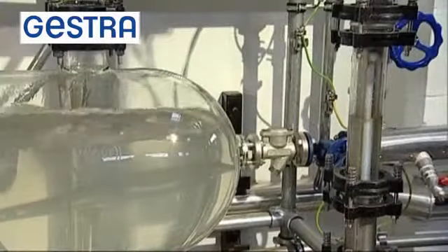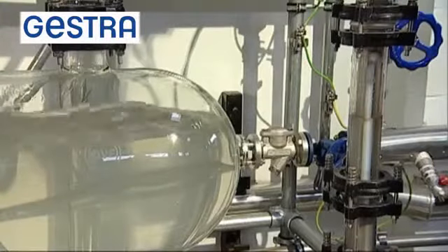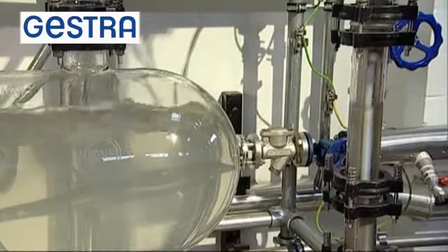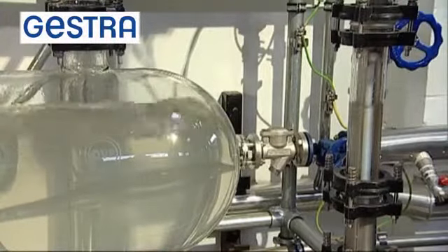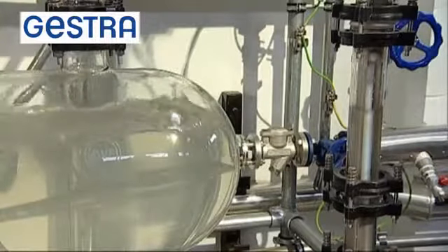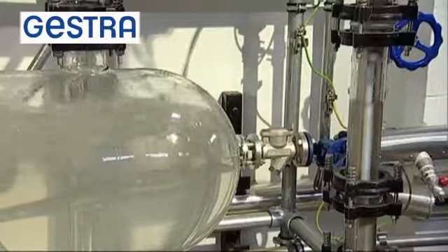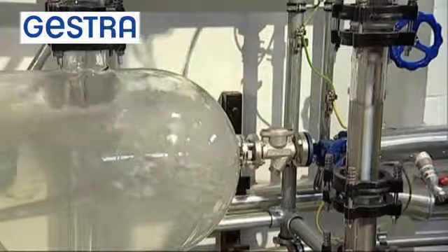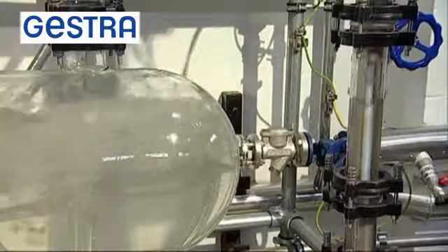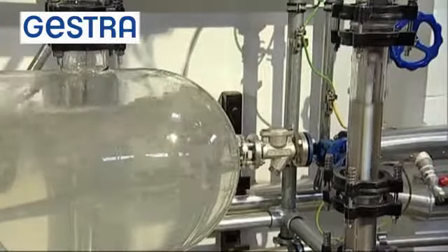Let's now try something else. Once again, the safety valve is opened, but this time is to simulate the effect of connecting major steam users to the system. Through the increased steam consumption, the pressure in the system falls. Right away, steam bubbles form everywhere in the boiler water, this being triggered by the pressure drop and the surplus heat or enthalpy.